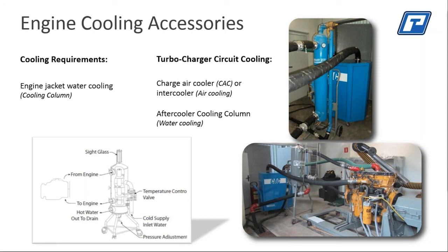Turbocharger circuit cooling is a little bit misunderstood. People say, oh, we don't need it. I can tell you this, I've had a lot of experience with this. If you do not use turbocharger cooling and you are trying to test to meet the standards as given by the manufacturer, you will not be able to reach the maximum output that is required on the test specifications.